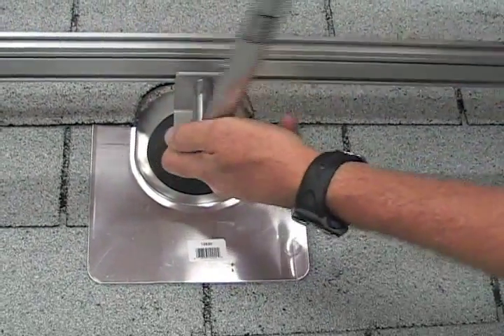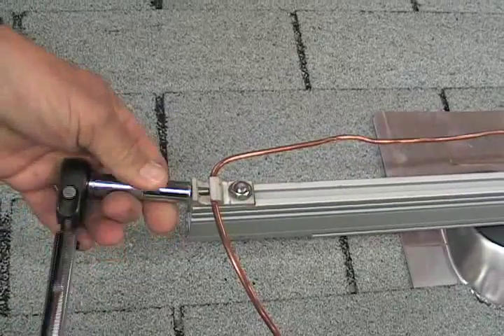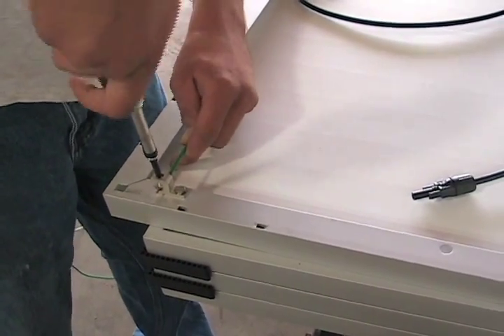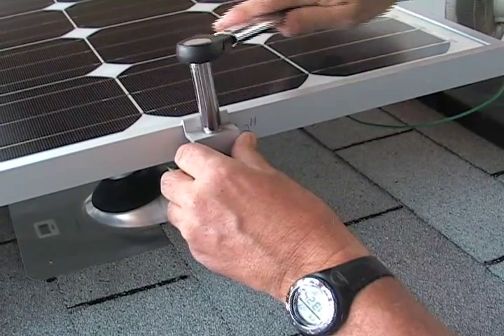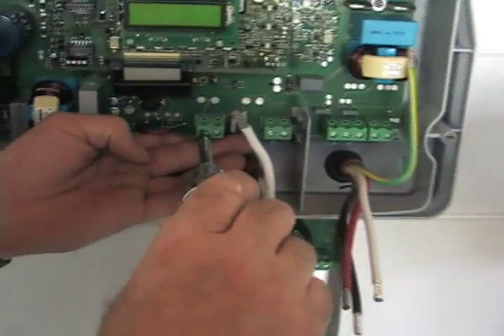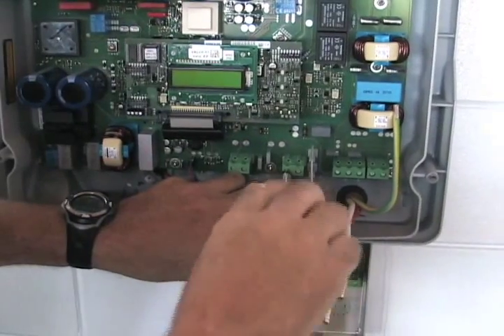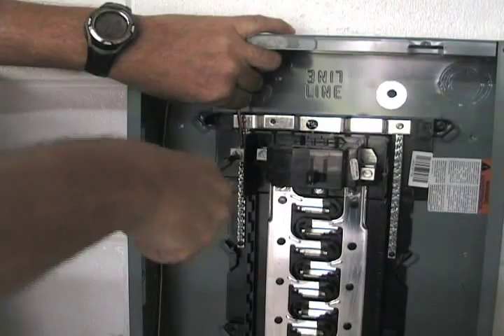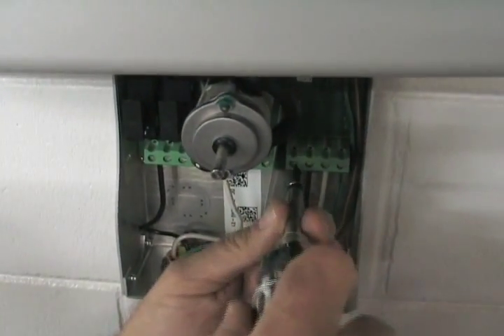What we're trying to demo here with torque tools is that in this solar system, once you put the legs into the rafter, when you start those standoffs with the L-feet, go through the Unirac rail system, the grounding, the Burndy lugs, the lay-in lugs, the split-bolt connectors, the inverter, the panel board, the breakers — everything, the manufacturer has a required torque specification. It'll click when we reach the setting. Torque, 20 inch-pounds.